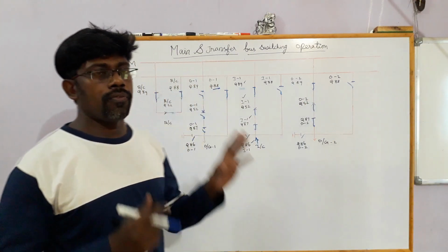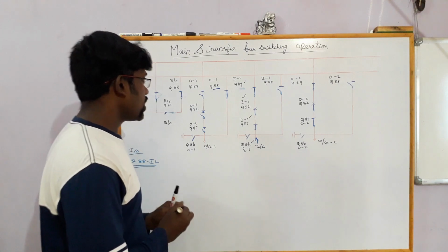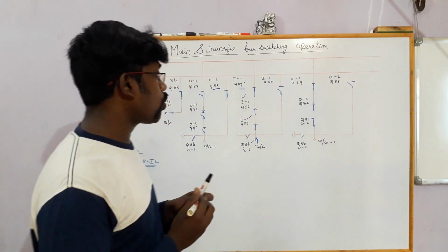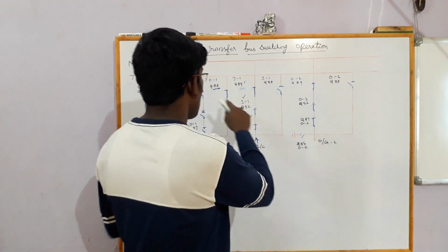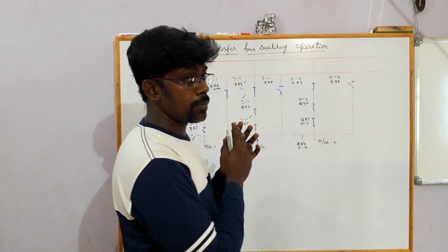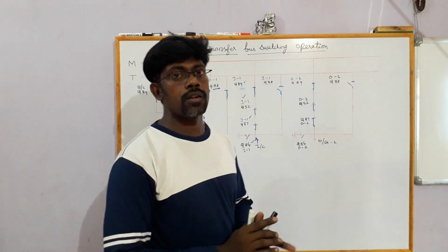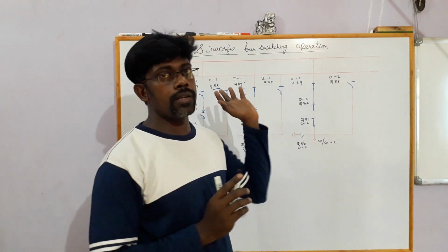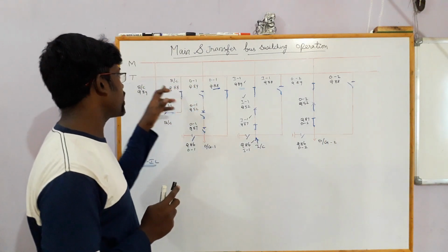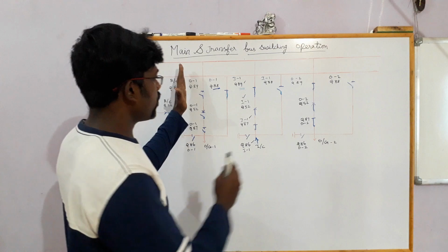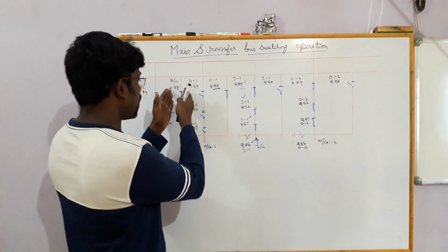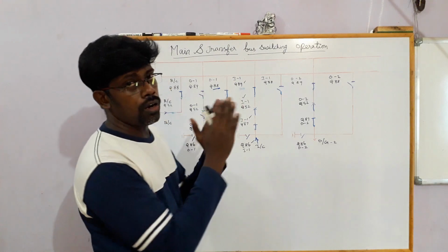So the first interlock for this is any Q88. If you want to close this Q88, all Q88 has to be in open position. That means no other feeder's bypass should be in closed position except bus coupler, because bus coupler Q88 is different. We only have to consider all outgoing. So the bus coupler will not come into the picture for all Q88.